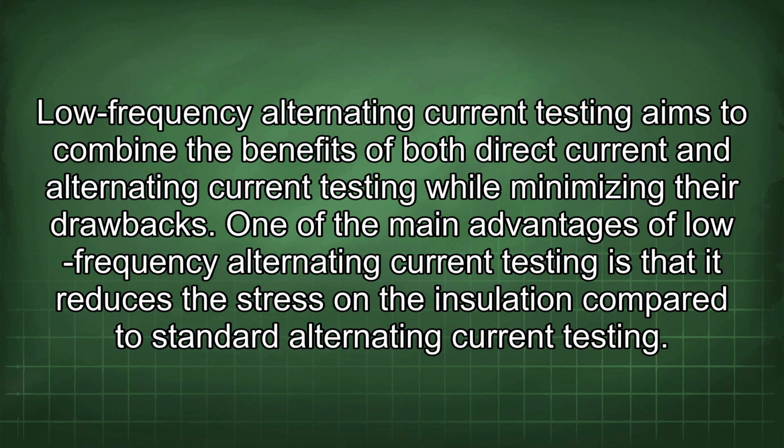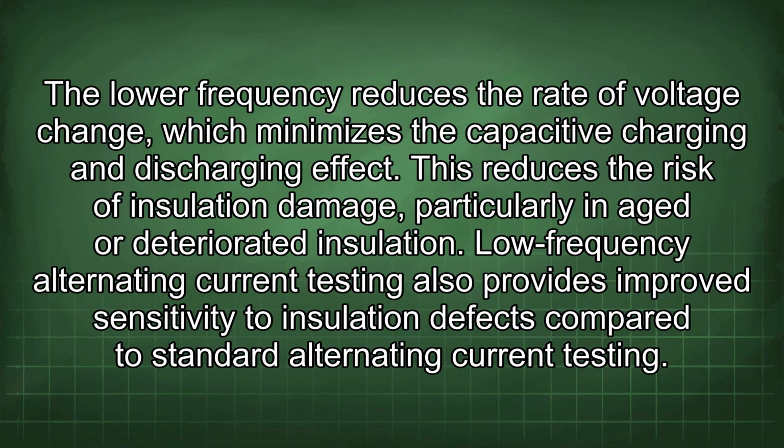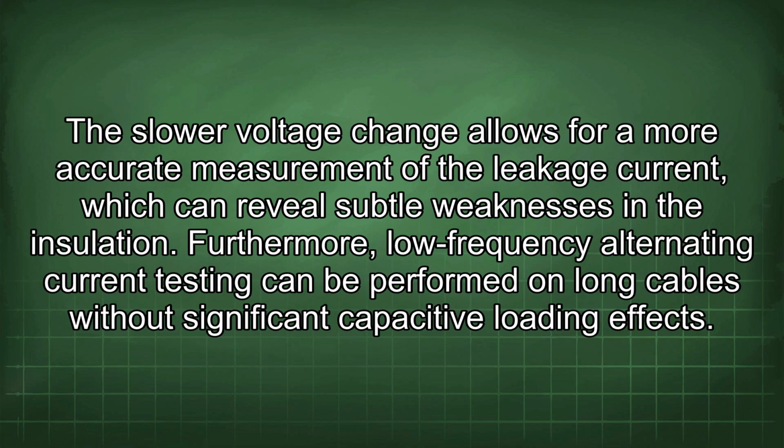One of the main advantages of low-frequency alternating current testing is that it reduces the stress on the insulation compared to standard alternating current testing. The lower frequency reduces the rate of voltage change, which minimizes the capacitive charging and discharging effect. This reduces the risk of insulation damage, particularly in aged or deteriorated insulation. Low-frequency alternating current testing also provides improved sensitivity to insulation defects compared to standard alternating current testing.